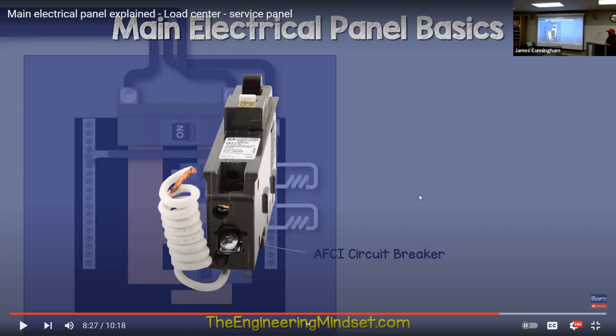Today, you can't do that. So each bathroom has to have its own circuit. Kitchen has to have at least 2 plug circuits. Outdoor plugs have to be on another circuit, garage plugs have to be on another circuit, so everything is divided out now. Everything is separated so you don't overload any circuit. So we're required to do that. And so now, instead of doing GFCI plugs, what is more traditional now is to do a combination arc fault GFCI breaker. It's a combination breaker that does both.